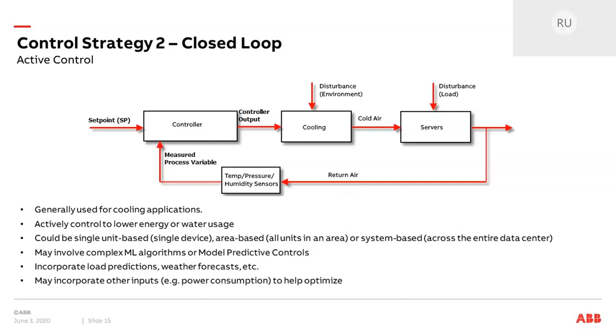The control could be simple or complex depending on what you're trying to do, and it can incorporate lots of different elements, like weather forecasts. You can also feed back more than just temperature information. One example, when we talk about a fully unified system, is looking at the energy consumed by the servers as well. That can be fed back into the control, allowing more complicated control logic within the controller that factors in total consumption by the servers to optimize around energy consumption.